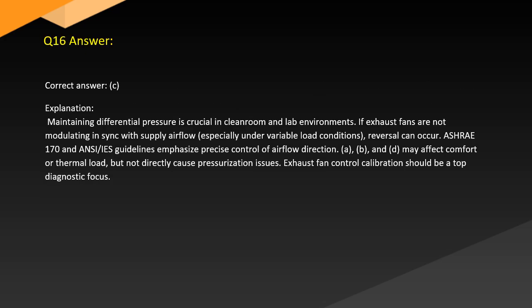Answer. Correct answer: C. Explanation. Maintaining differential pressure is crucial in cleanroom and lab environments. If exhaust fans are not modulating in sync with supply airflow, especially under variable load conditions, reversal can occur. ASHRAE 170 and ANSI guidelines emphasize precise control of airflow direction. A, B, and D may affect comfort or thermal load, but not directly cause pressurization issues. Exhaust fan control calibration should be a top diagnostic focus.